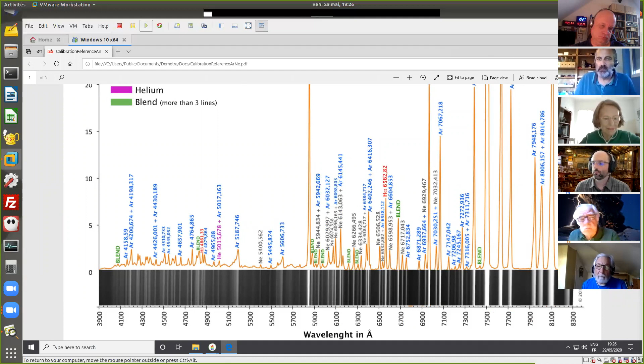When I look at the neon argon spectrum, we have some lines that are well known. The most important lines here are considered reference lines, and these reference lines are listed here. This list is very critical because it is the list we use to make the automatic calibration. By the way, you can access the reference documents by clicking on this button, the show reference document. So you have direct access to this document, and maybe we have to improve it, but anyway, it already exists in this format, and that's not so bad.